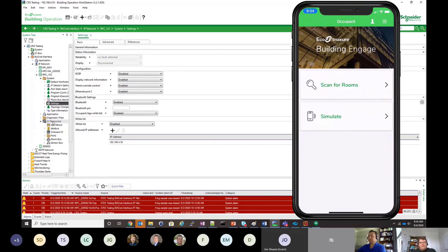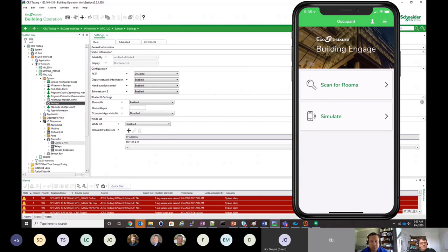We're used to having all of our I/O terminal references on the onboard I/O, in the onboard I/O area. Sensor bus, we're used to that from any living space sensors you have that show up in that menu. And then room bus, that is where for the new RPCs, your connected room solution modules show up. So I've got a few on my RPC here.